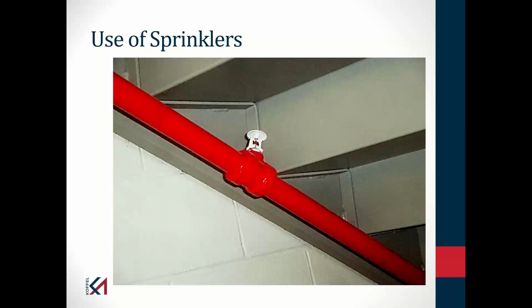You don't want to have an upright sprinkler like we see here, and you decide to lay an acoustical tile, and you now take that upright sprinkler and simply rotate that elbow 180 degrees, and that sprinkler is now in a pendant position, because that sprinkler is going to cause the water to go up towards the ceiling if you do that.